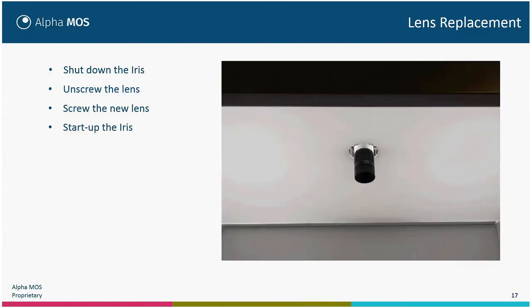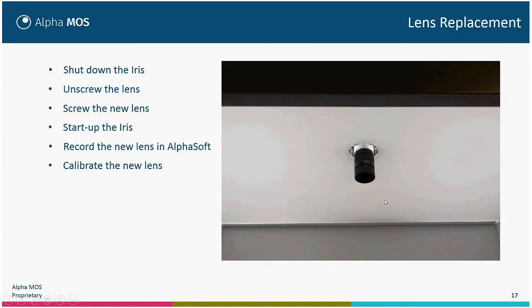Once the new lens is installed, start up the iris. You will have to record the new lens in AlphaSoft and perform a calibration for the new lens — adjusting the focus and the diaphragm — because these are not set at the beginning.